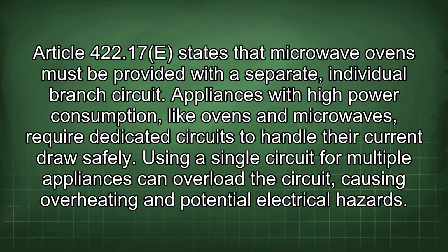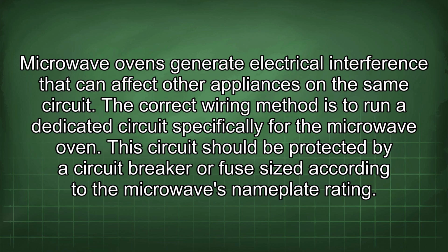Article 422.17e states that microwave ovens must be provided with a separate, individual branch circuit. Appliances with high power consumption like ovens and microwaves require dedicated circuits to handle their current draw safely. Using a single circuit for multiple appliances can overload the circuit, causing overheating and potential electrical hazards. Microwave ovens generate electrical interference that can affect other appliances on the same circuit.